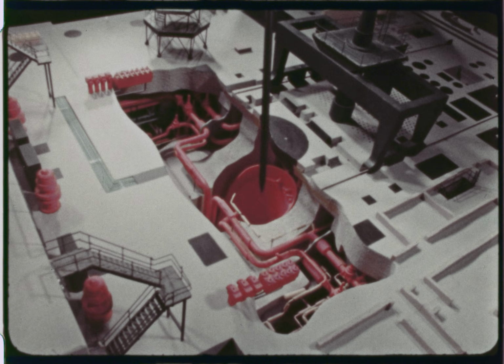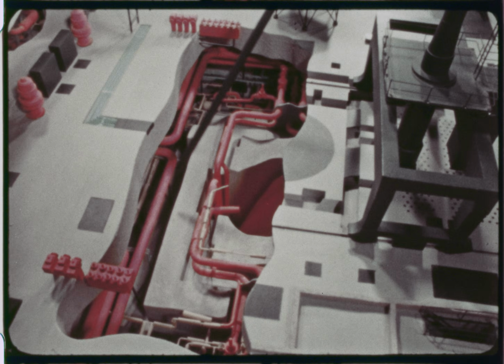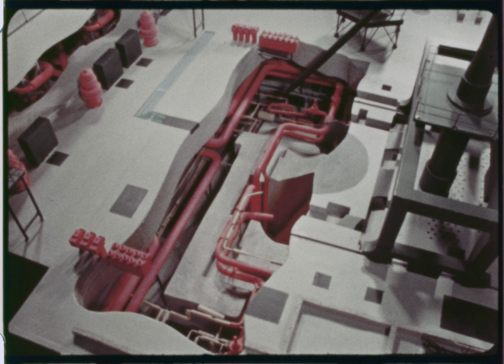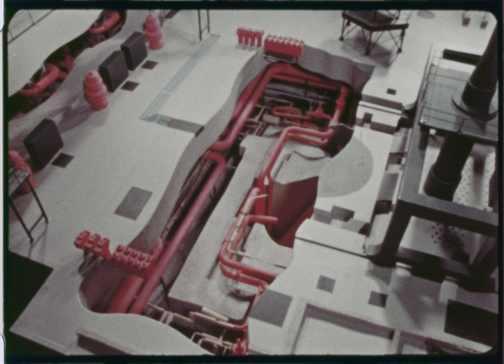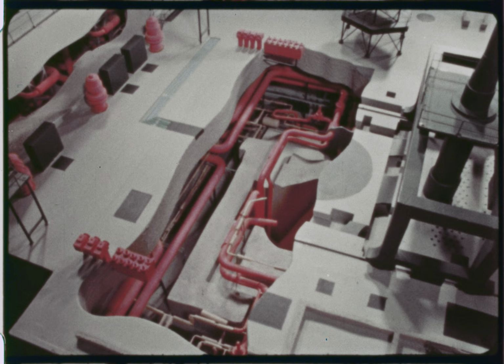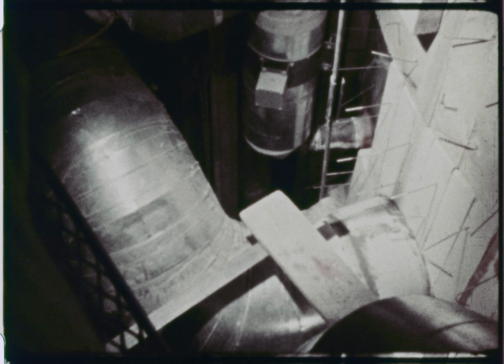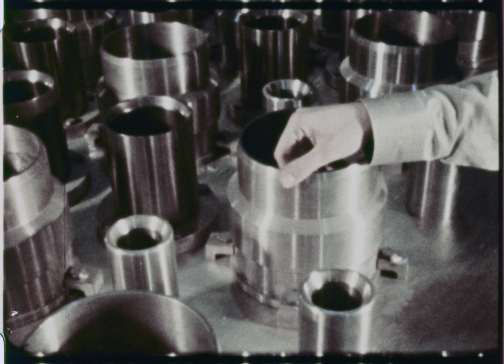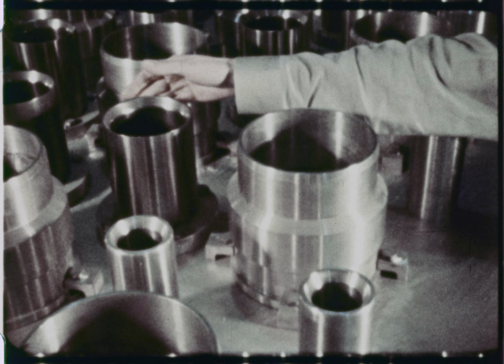The reactor vessel and the primary sodium system are surrounded by a series of steel-lined concrete cells. These nitrogen-filled cells would prevent the escape of radioactive sodium vapor or fission product gases into the atmosphere and radioactive liquids into the surrounding subsoil. 3 main sodium inlet nozzles are located 28 inches above the base, and 3 sodium outlet nozzles leave the vessel 23 feet above the base. At the top, a stainless steel bellows assembly seals the reactor vessel to the upper cavity liner to prevent sodium vapors and the helium cover gas from escaping. Within this vessel, liquid sodium flows through the core at the rate of 21,600 gallons per minute. A stainless steel grid plate is supported 42 inches above the bottom of the core tank by individual columns and a support ring. The grid precisely locates the moderator elements with relation to the fuel elements.